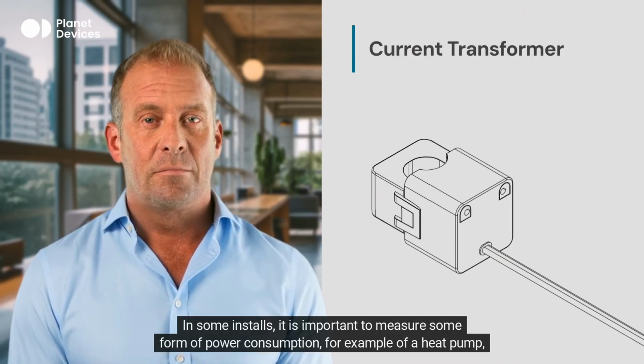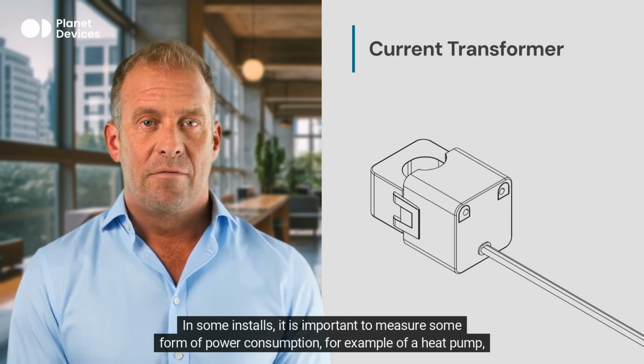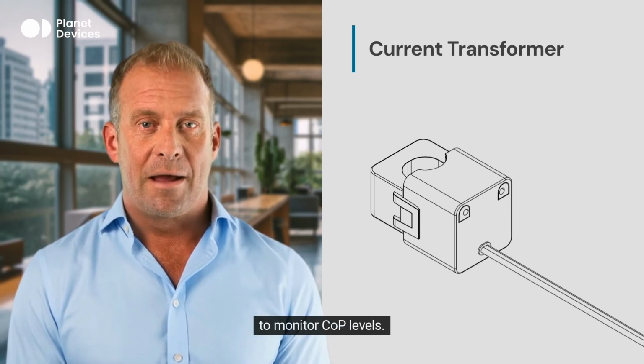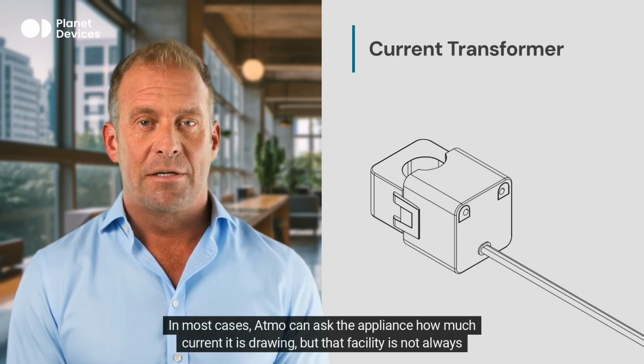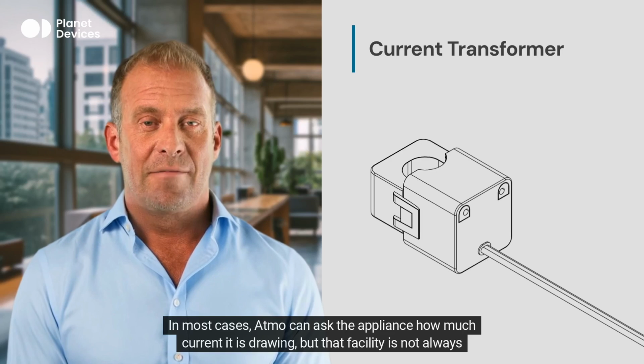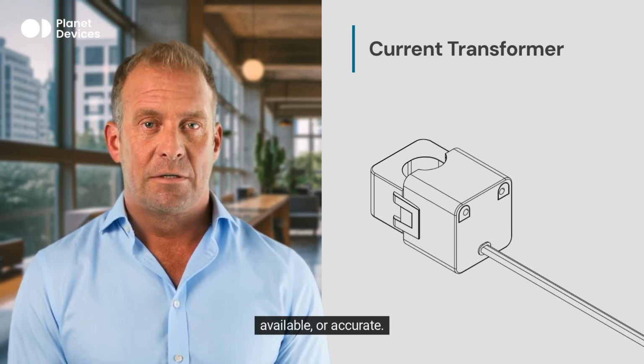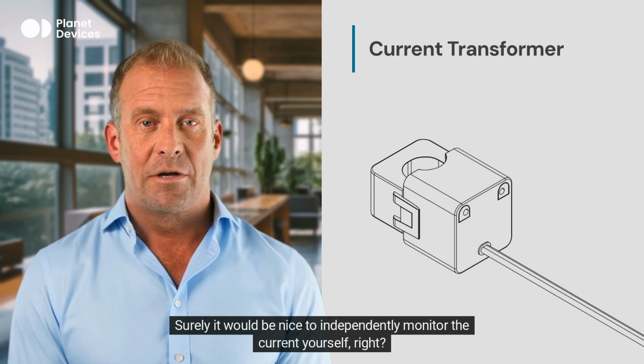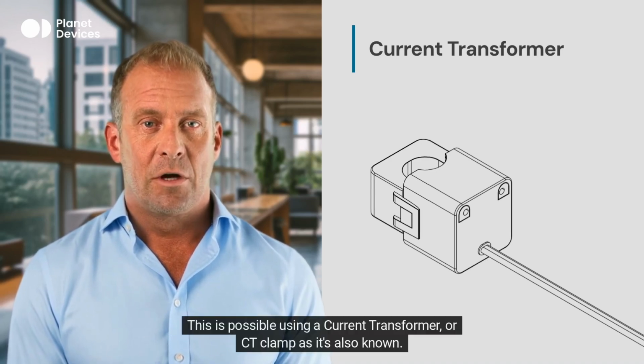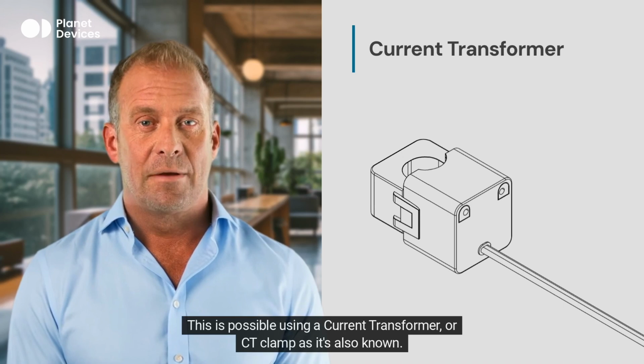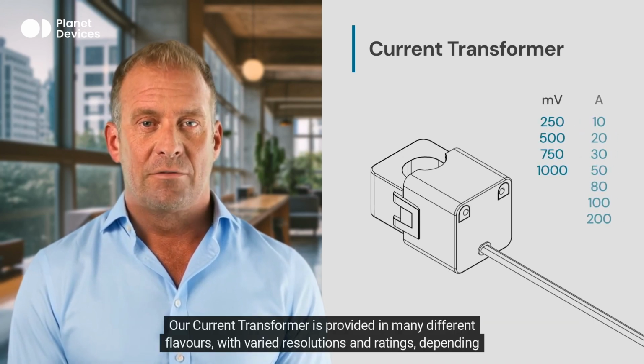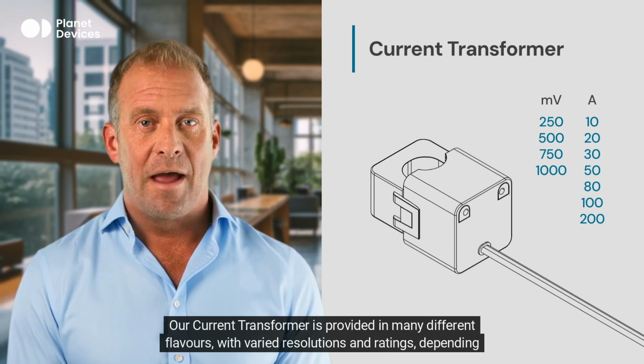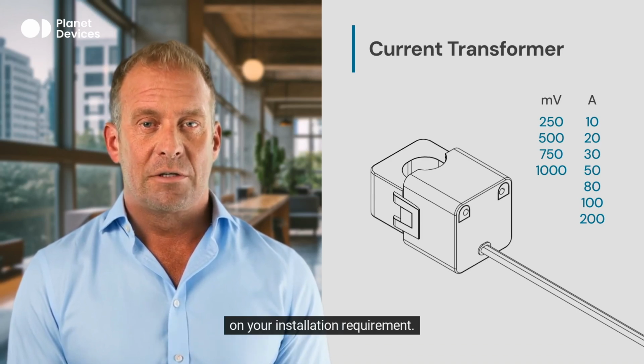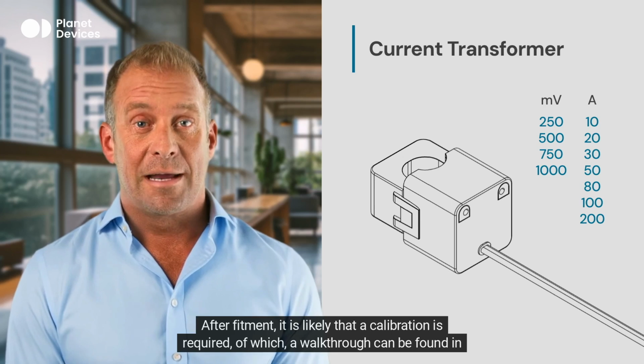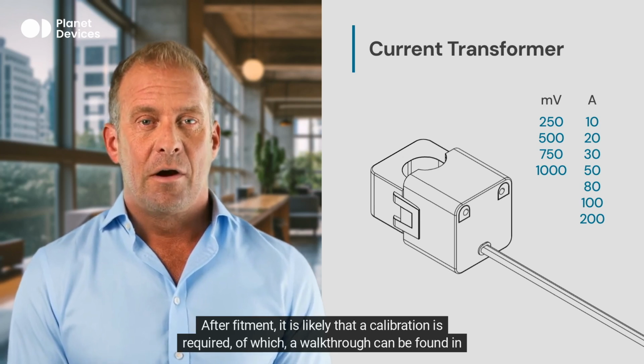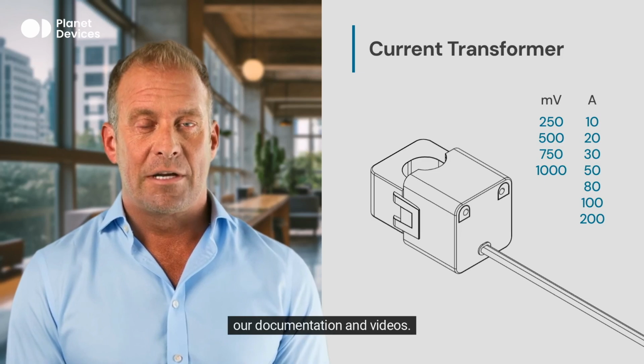In some installs, it is important to measure some form of power consumption, for example of a heat pump, to monitor COP levels. In most cases, Atmo can ask the appliance how much current it is drawing, but that facility is not always available or accurate. Surely it would be nice to independently monitor the current yourself, right? This is possible using a current transformer, or CT clamp as it's also known. Our current transformer is provided in many different flavors, with varied resolutions and ratings, depending on your installation requirement. After fitment, it is likely that a calibration is required, of which a walkthrough can be found in our documentation and videos.